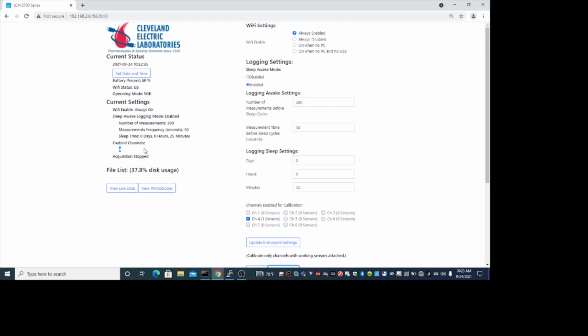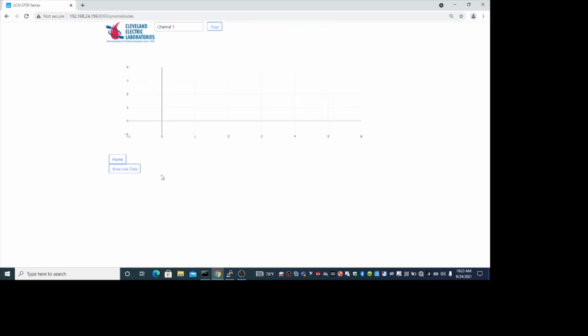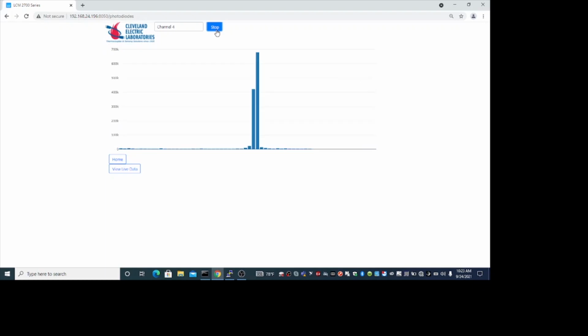We can also further look at the calibration. We can view the photodiodes. Go to channel 4 and click Start. It will show a histogram of the light being reflected back through the fiber Bragg grating. So you can see the histogram here. That looks good, so we'll go ahead and stop that.